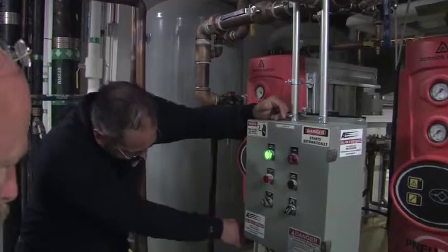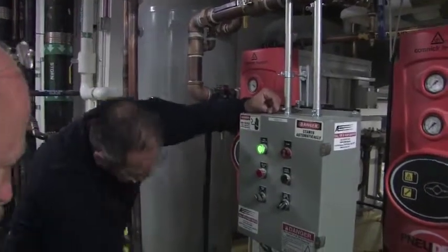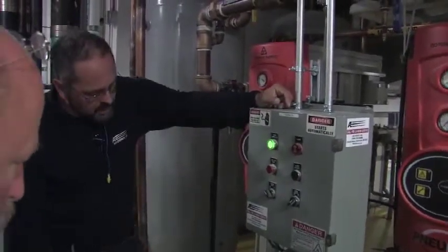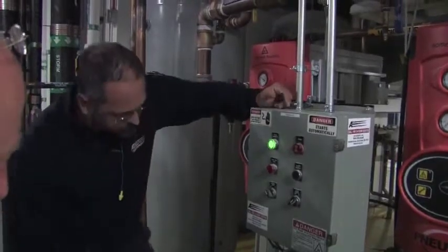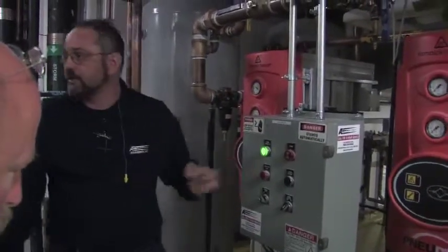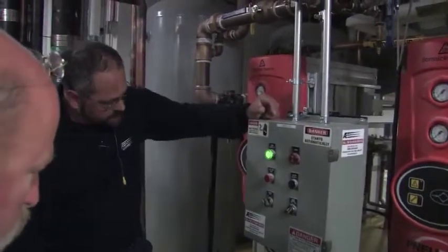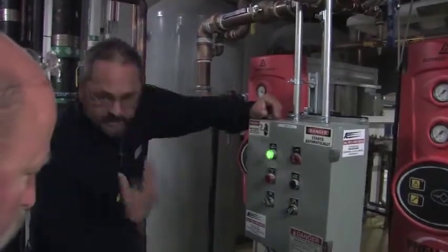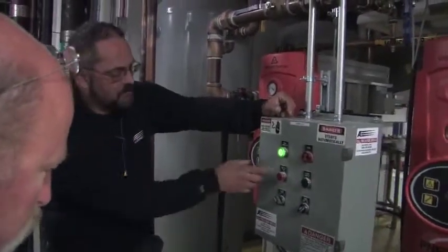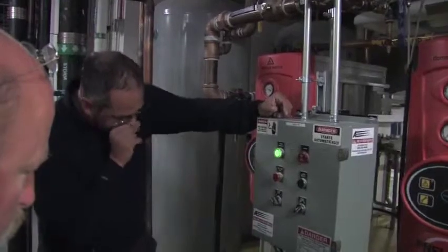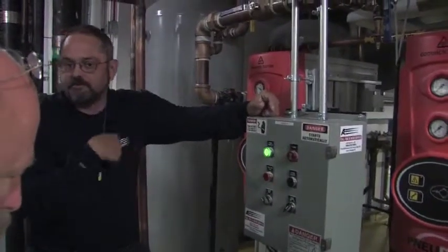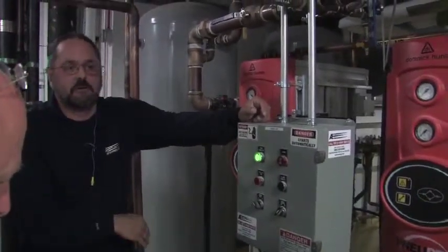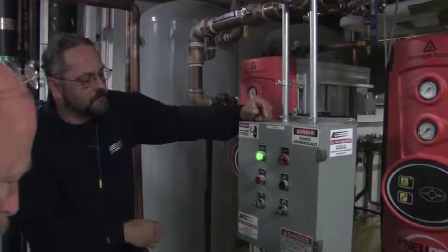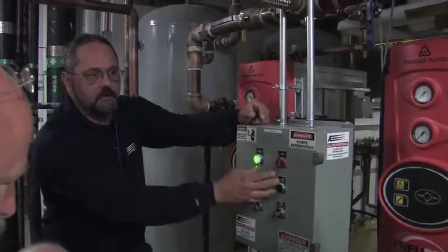Okay, the other thing that's plugged in here is the carbon monoxide monitor. The carbon monoxide is plugged into there. Dew point's got 24 volts coming from here. This dew point monitor has 2 set points, one for the alarm, the local alarm here, which is the standard, triggers at 35, resets at 32. If it triggers, you have to clear it here if it's latched.